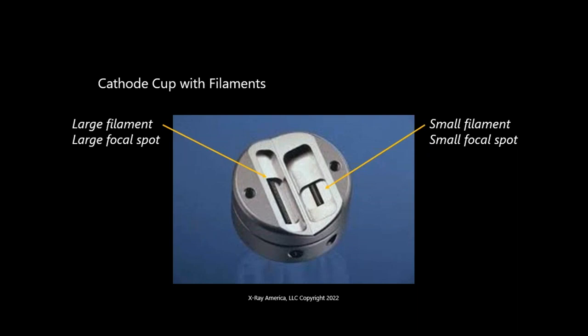And you can start getting into the nitty-gritty, but based on what we've seen, my company started loading the Toshiba product line back in the day, and that was one of the biggest issues versus Varian at the time. They couldn't get the alloys correct on the filaments, so their emissions were not correct. Varian actually has a very high emission output, and it must be really good material for the filaments. It took Toshiba a couple of years to get back to having good tubes.